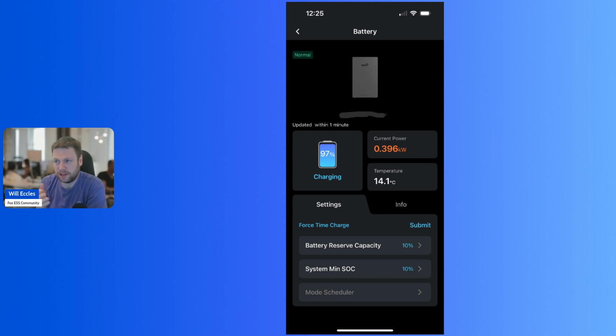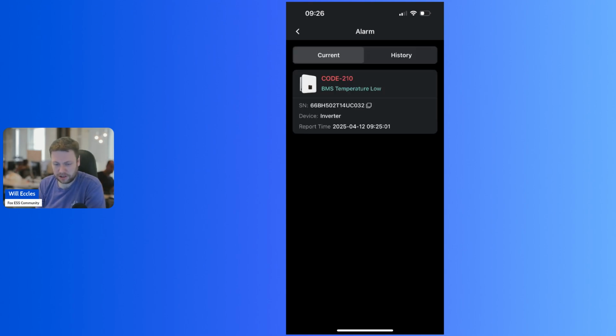So why are we talking about the error code and the battery temperature? If the battery temperature gets too low, typically low single figures, the battery will try to protect itself and it will stop charging and discharging. The exact temperature differs per battery model, the environment it's installed in, indoors or outdoors. It also depends on the firmware installed on the battery as well as the inverter. But when it gets close to 0 or colder, sometimes I've seen 3, 4, 5 degrees cause an error code 210, BMS temp low.